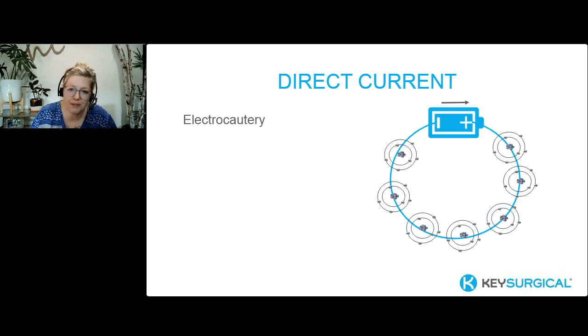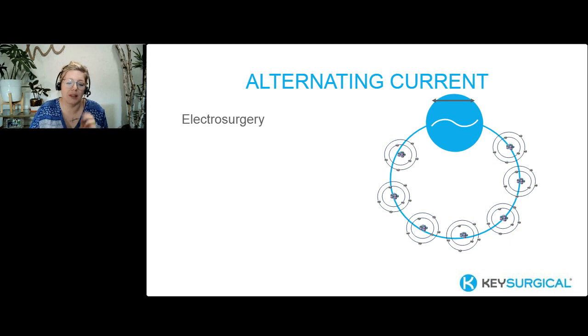In electrocautery, we're using direct current. We have this all in one direction, and the significance for this is that when we talk about heat in a second, when you're using an electrocautery device, heat is created in the device and then applied to the patient's tissue, versus when we talk about alternating current. And this is what we use for electrosurgery. So you can see that visual here as well. We have that alternating current. And as we go forward in talking about heat, it's great to understand that it's not the device that's being heated up. The heat is actually generated inside the tissues, inside the cells.